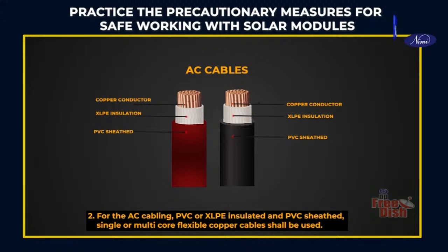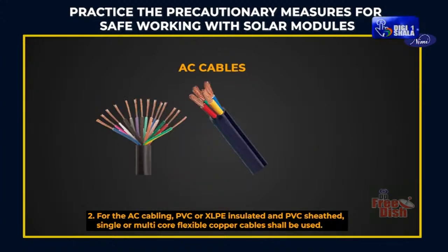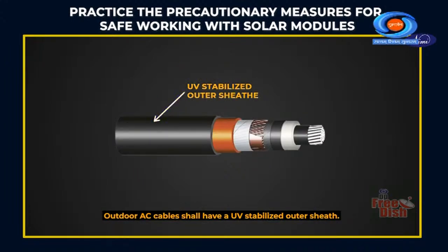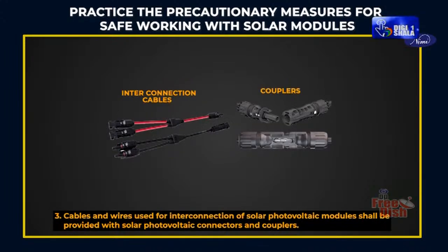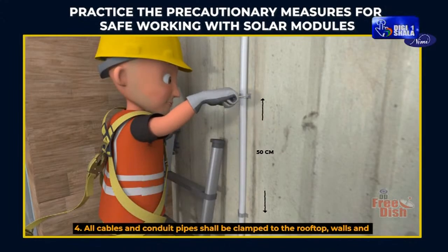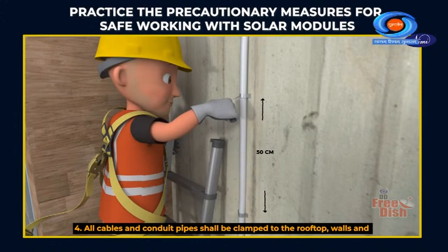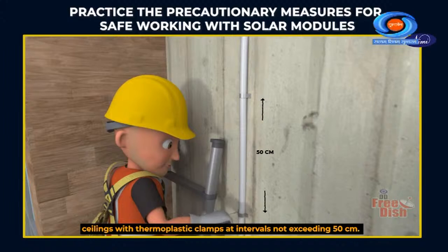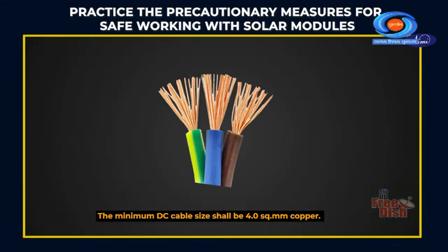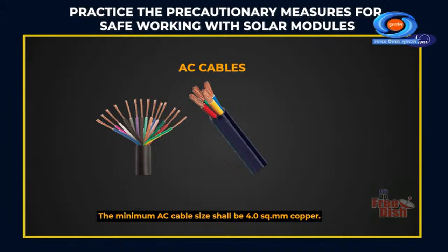For the AC cabling, PVC or XLPE insulated and PVC sheathed, single or multi-core flexible copper cable shall be used. Outdoor AC cables shall have a UV stabilized outer sheath. Cables and wires used for interconnection of solar photovoltaic modules shall be provided with solar photovoltaic connectors and couplers. All cables and conduit pipes shall be clamped to the rooftop, walls and ceilings with thermoplastic clamps at intervals not exceeding 50 centimeters. The minimum DC cable size shall be 4.0 square mm copper. The minimum AC cable size shall be 4.0 square mm copper.